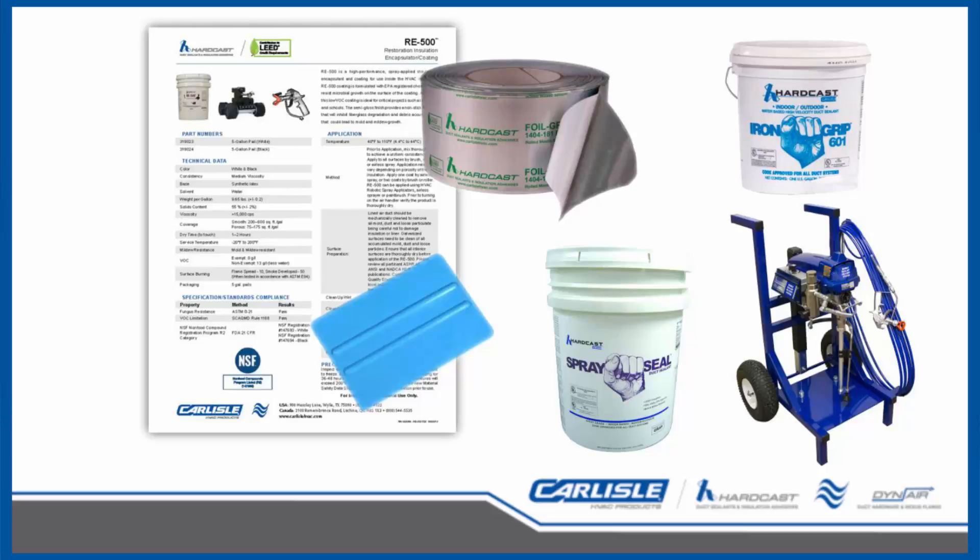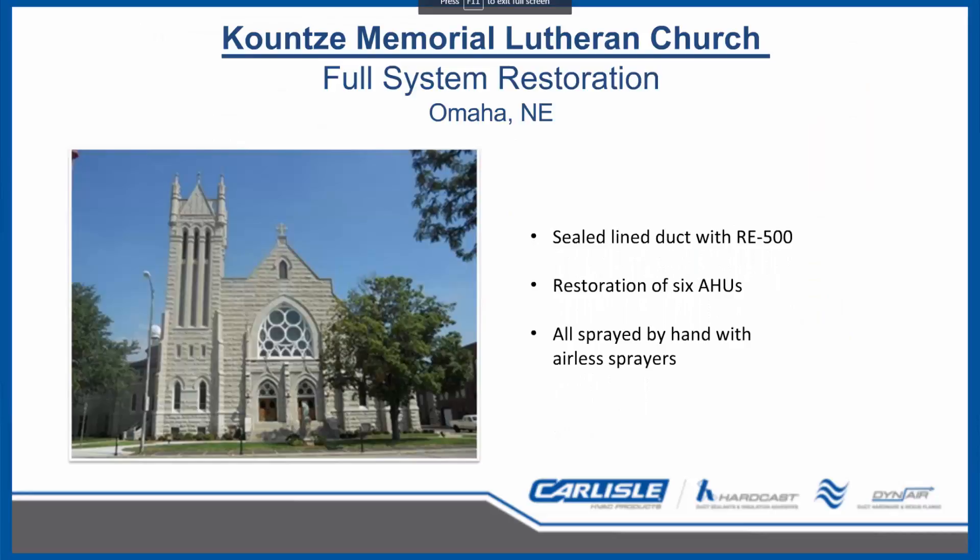Let's look at a few examples of projects where Carlisle HVAC restoration products were utilized. Kountze Memorial Lutheran Church in Omaha, Nebraska, built in the early 1900s, underwent a full mechanical system upgrade. Engineers decided to utilize Carlisle HVAC's RE500 to resurface all of the church's ductwork. Instead of tearing out and replacing all of the internal duct insulation — which would cost tens of thousands of dollars and force the system to be shut down for weeks — engineers specified RE500, which was installed over the fiberglass duct insulation as well as the internals of six air handlers.